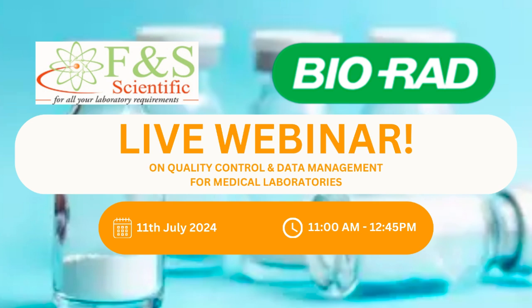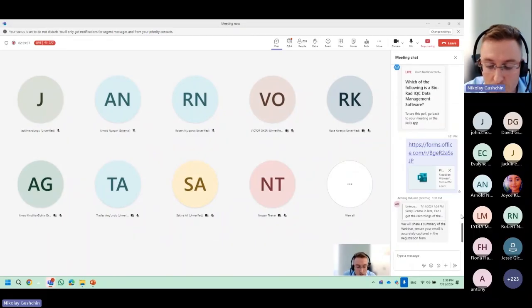Yeah. Okay. Thank you very much. It's a very good question. So when we are speaking about the comparison between the instrument manufacturer controls and independent controls, the first thing is about independence, independent assessment. If you open the insert for the manufacturer QC, you will see the data for only a specific reagent or only one instrument. So that means that this QC material can be optimized in a way to work with good results with this specific test system. So it can be not so sensitive to catch the errors, to catch the issues with the test system. This is one thing.